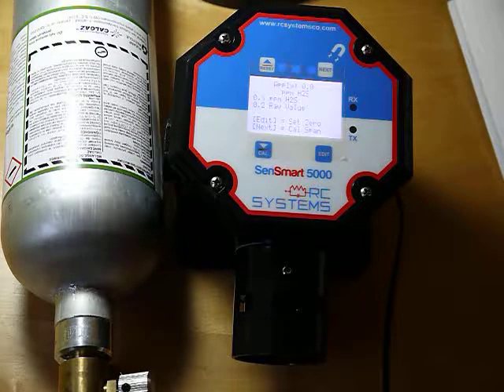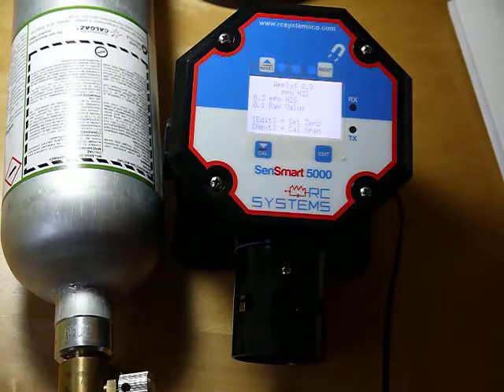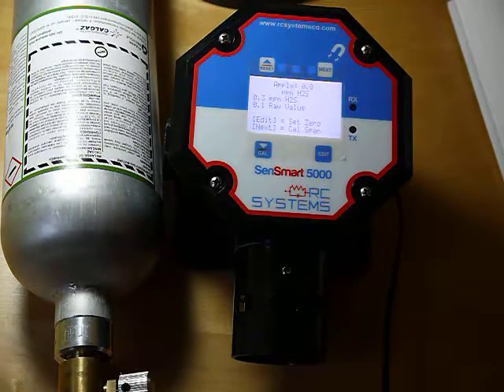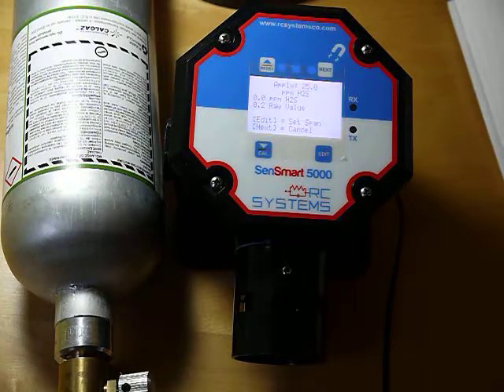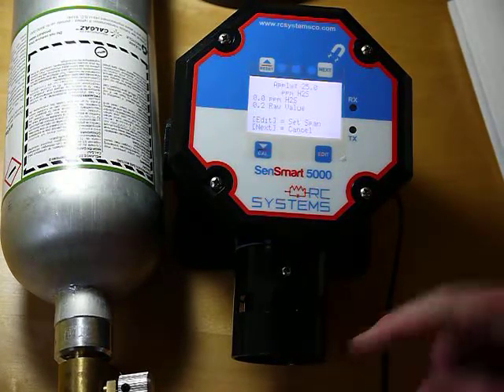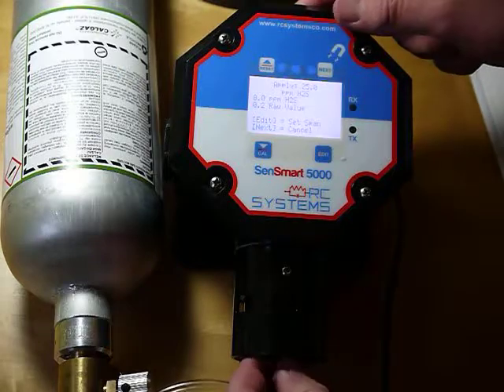The air in here, you know, if you were in an area where there may be H2S, you'd want to use a cylinder of clean air. I know in here there should be no real H2S in the area, so I'm going to hit edit, and that sets the 0. Now it says apply 25 ppm of H2S.